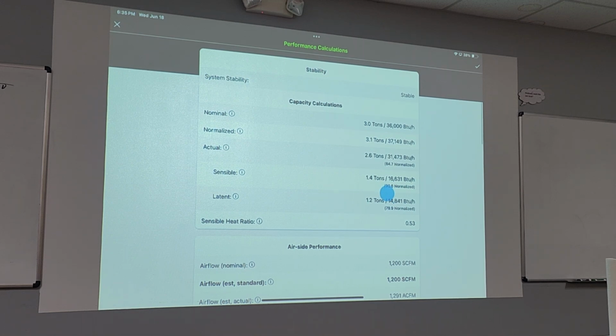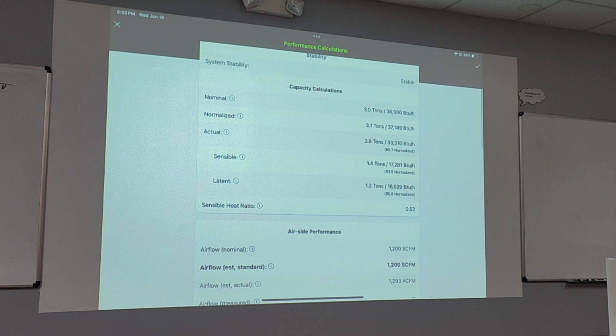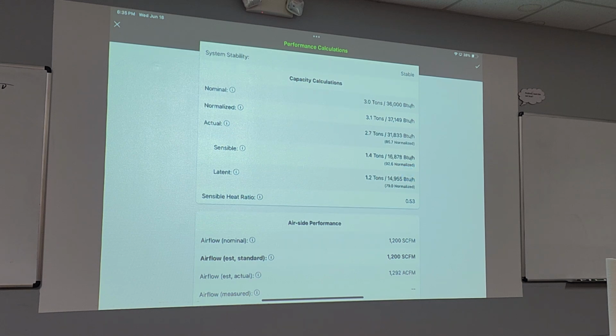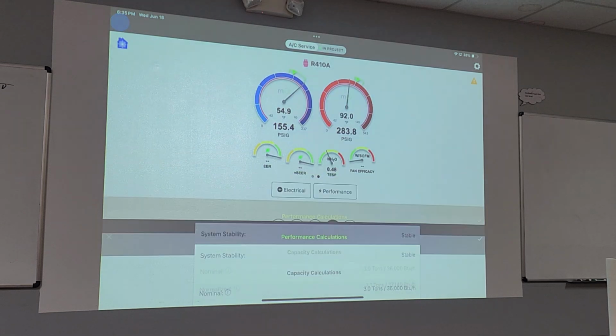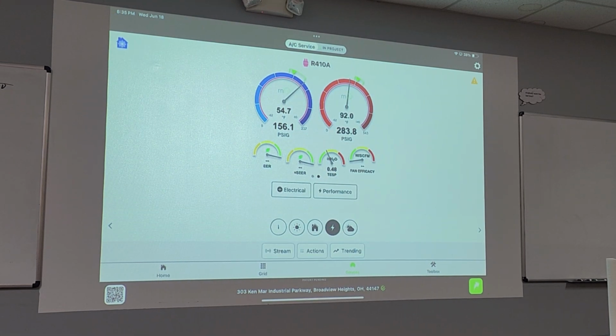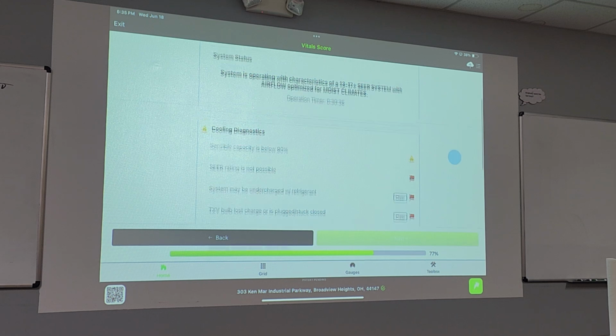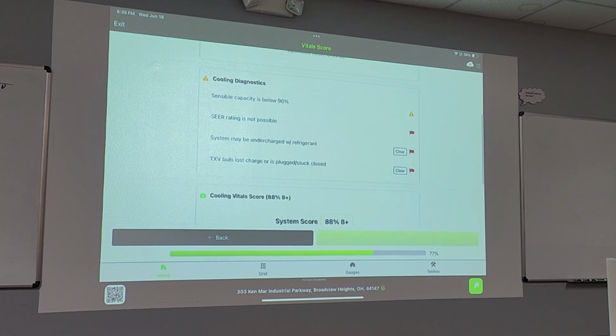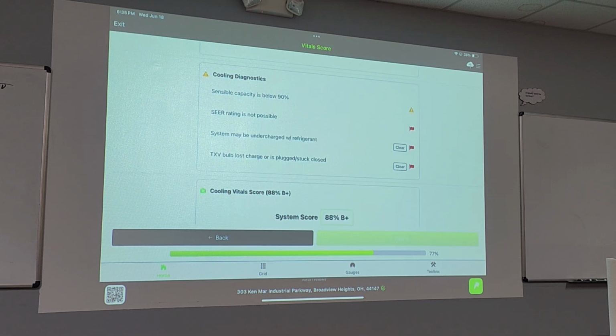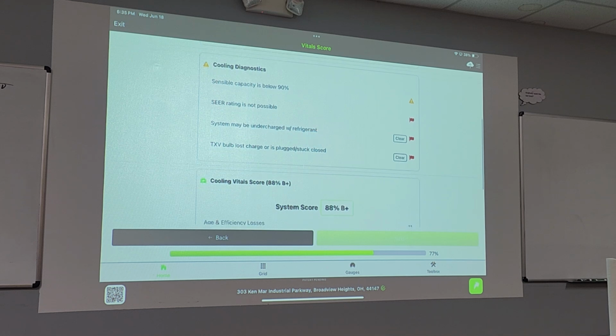Here's my sensible capacity. That's a live calculation right now. 93.5%. And if it crosses below 90, it will probably throw that fault code up. So it's just yes or no.